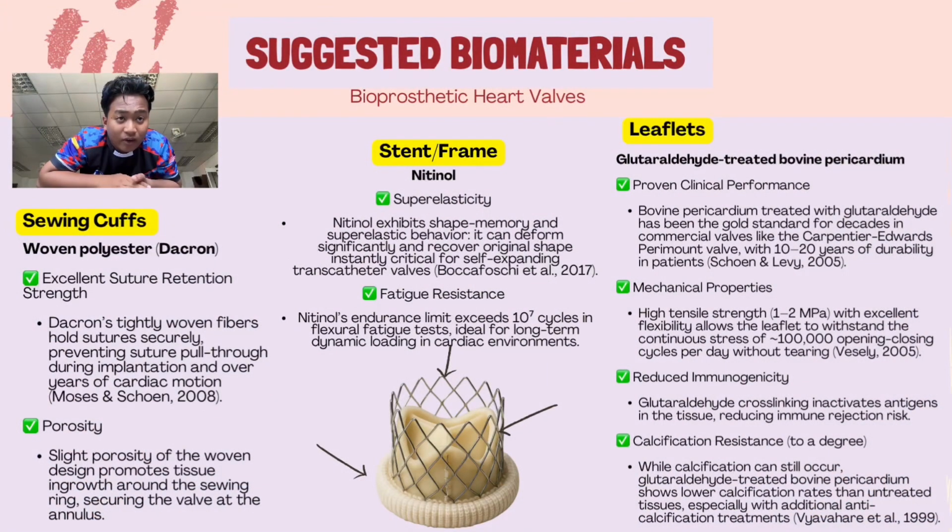Firstly, the sewing cuff. I propose woven polyester or Dacron due to its high suture retention strength and slight porosity, which promote tissue ingrowth for secure fixation. Second, the stent. I recommend nitinol, a nickel titanium alloy with superelastic properties, perfect for a self-expanding valve and exceptionally fatigue resistant for millions of cycles.